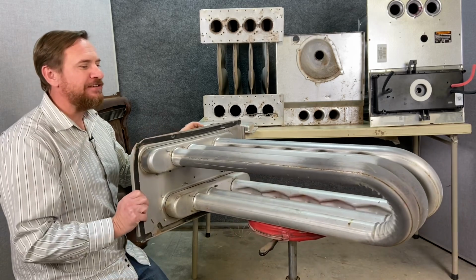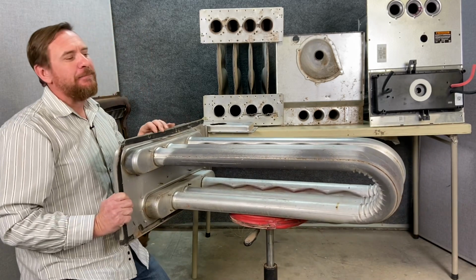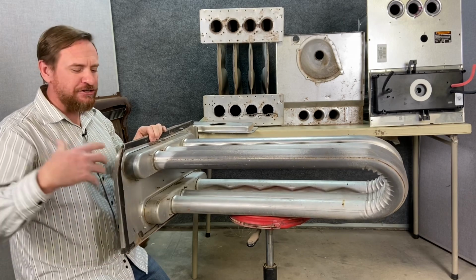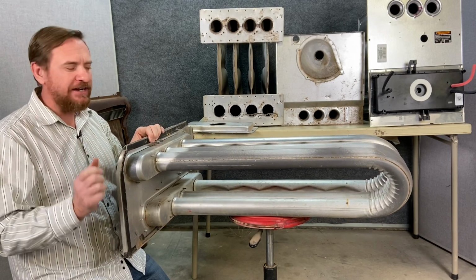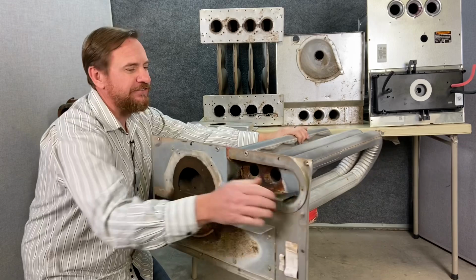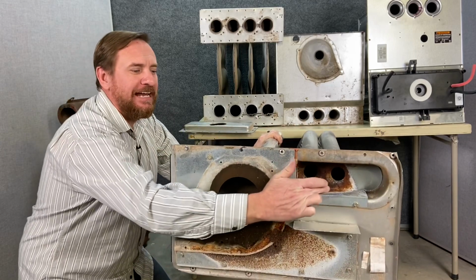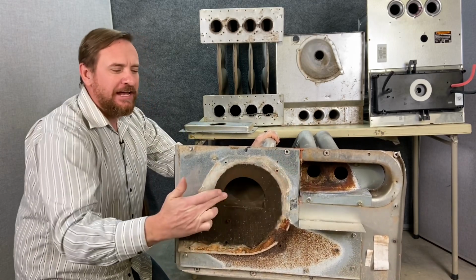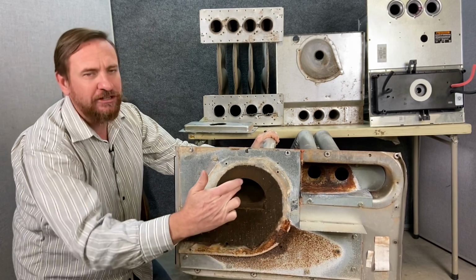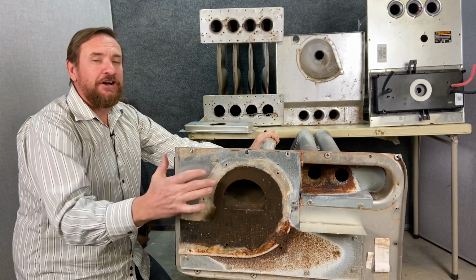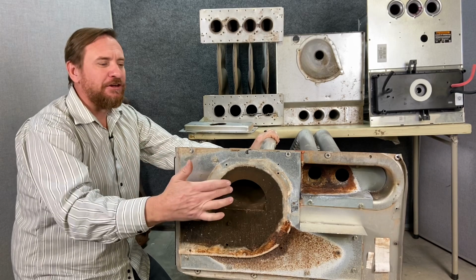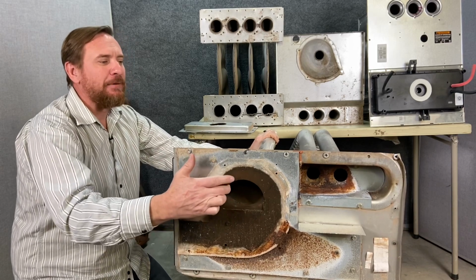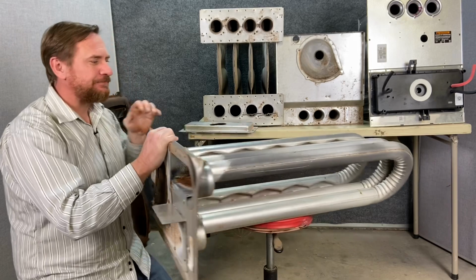On package units, they were much more likely to fail because of the weather. The package unit was exposed to outside moisture and air, and it caused a significant amount of rust. And in this particular model, you can see a large amount of rust here. Also, on this, we see there's a lot of soot. It was actually caused from improper gas pressure. It wasn't having the correct air-fuel mixture, and it actually sooted up all the way inside this heat exchanger.